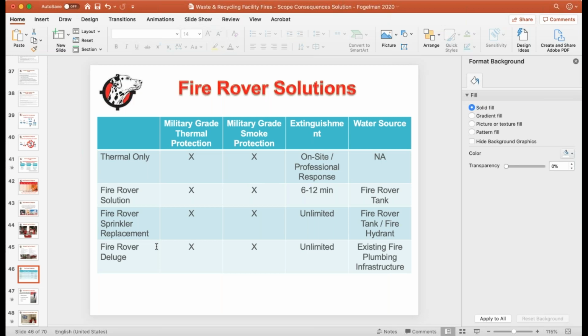So what we've done is shoot for this location. We have three boxes around the location, and then we have a manifold off the back that the fire department can connect to. So when the fire department gets there at the 8 to 12 minutes when we've extinguished our tank, they can connect to the back, and we'll continuously shoot out our solution for as long as we can, targeted towards the actual heat, which is exactly what we need to do.